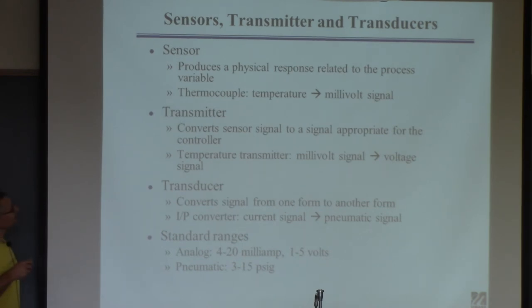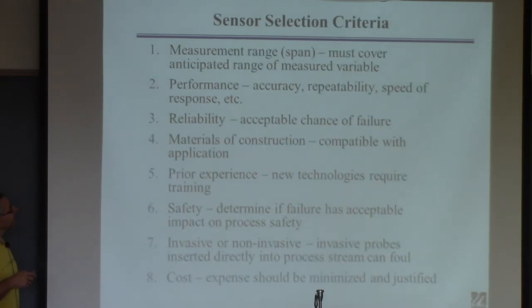Transducer is something that converts one signal to another. The only one we're usually really concerned with is I to P, right? That's a device that takes an electrical signal from a controller and creates a pneumatic signal that drives a valve. And the units of these things are really bizarre. So if you look, analog signals mean, you know, voltage and current signals, pneumatic mean air pressure signals. These are the typical ranges for historical reasons. So something's in milliamps. It's 4 to 20 milliamps. If it's voltage, it's 1 to 5. And its pressure is 3 to 15 PSIG. So in other words, if you have a valve driven by pressure and you apply 3 PSIG, the valve will be completely open. But if you apply 15, it might be completely closed. Just the way it works when you keep doing that. All right. So, and again, the key things here are your ability to measure and your ability to actuate. All right. So these are the things that you take into account when you pick a sensor. So let's say you're in a plant. Again, when you're doing control in a plant, there's two possibilities. One is that it's a brand new plant. And you're just doing everything from scratch. It's just from the grassroots project, they call it. Or you might be doing an improvement project. And you tell someone, if we just had the composition of this intermediate stream, we could do this. And it would be great. So then you have to, I told this before, you have to justify the cost. But if you can do that, eventually you have to pick a sensor.